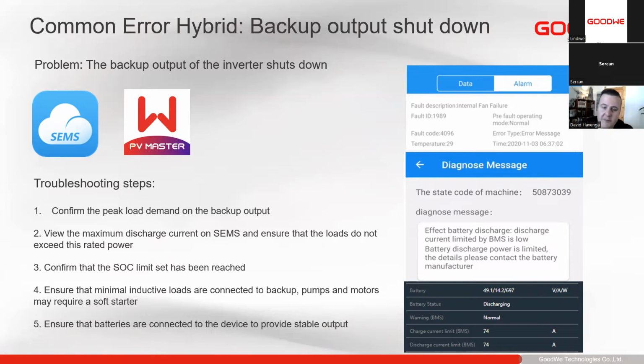We can also view the maximum discharge and charge current on SEMS portal. As you'll see in this example here, we only have 74 amp charge and discharge. This is a 4.6 kilowatt inverter. At 74 amps at 49 volts, we only have about 3.5 kilowatts of discharge power available to us. So should our loads be larger than that, even though the inverter can do it when there is utility or solar, when we only have batteries, we are limited to that battery discharge power limit.